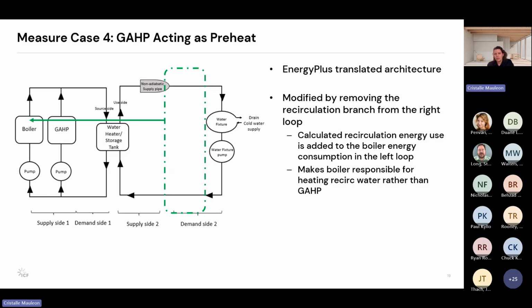This is showing that the GAHP is only preheating incoming cold city water, and the boiler is solely responsible for reheating the recirculated water. The GAHP and the boiler are still operating in parallel with respect to the storage tank, and the load distribution scheme is still set to optimal in EnergyPlus. Again, the storage tank outlet temperature is set at 135 degrees. This approach reflects a common industry configuration where the recirculation is handled by the boiler and the city water is preheated by the GAHP.